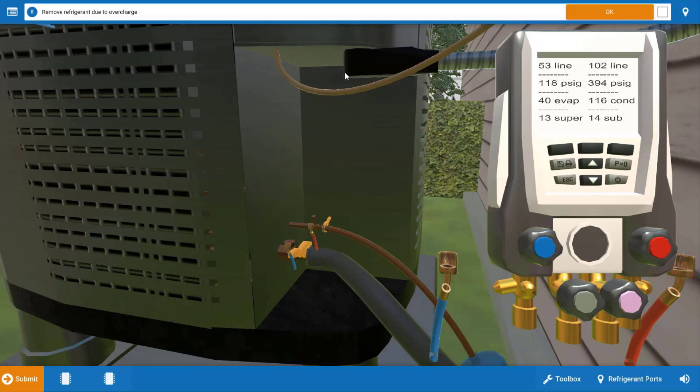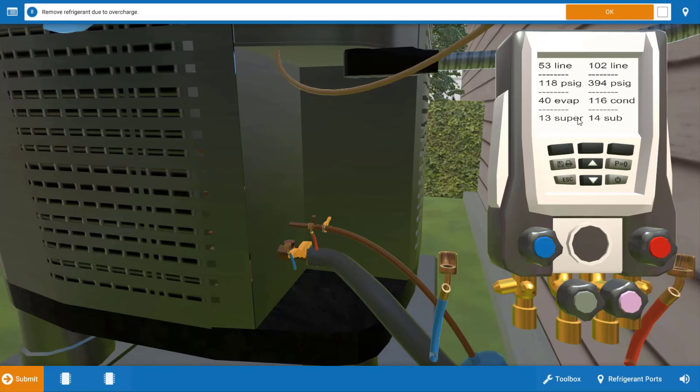We've done this and if we look now we can see that our pressures, evaporating and condensing temperatures, are now normal and if we look at our subcooling margin we're within three degrees of that target of 13. We've got 14 now so we've solved this problem.